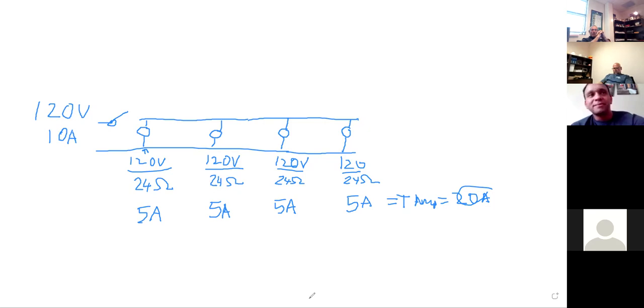Okay. All those variables that you have there, voltage, resistance, whatever, they can all change in the world. But the factor that opens and closes a breaker in a substation is amps. The reason I go into overload is because of amps. Load exists on the circuit, whether it's closed or open. Amps.